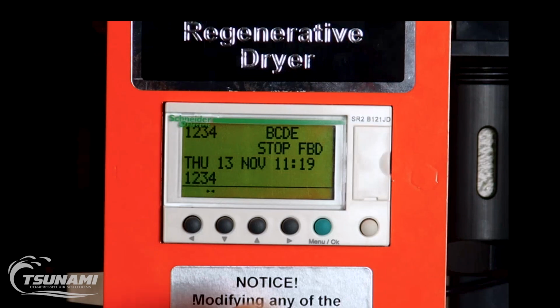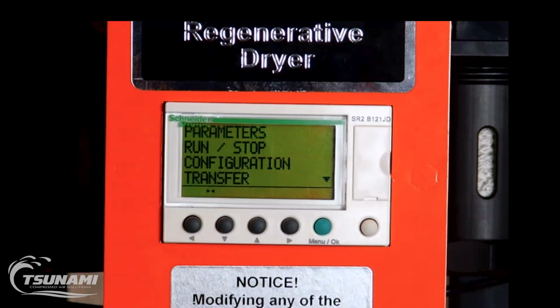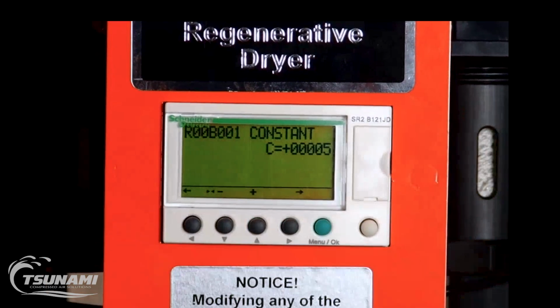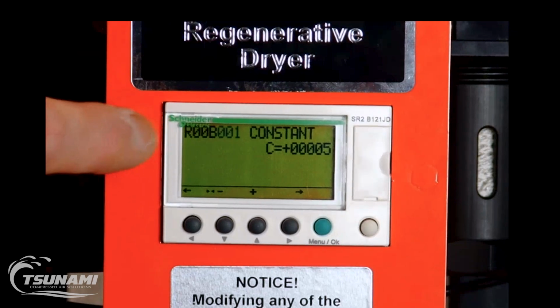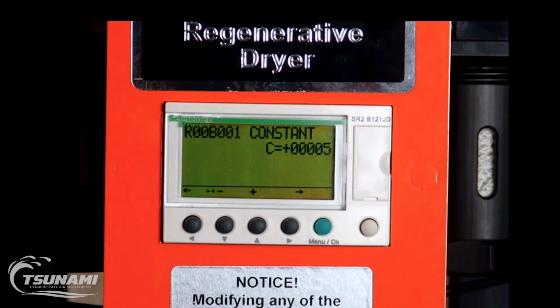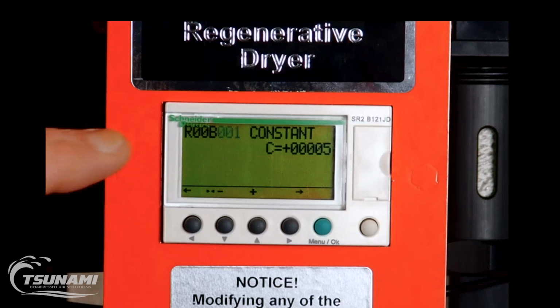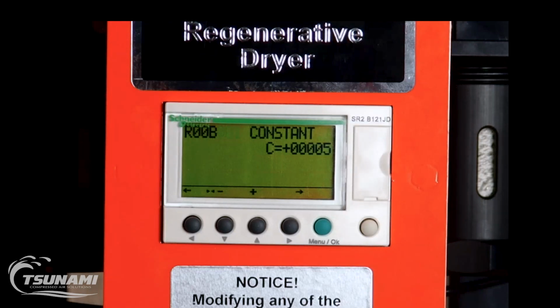Now that we're in the stop mode, we can access the parameters. Parameters is flashing. We hit the menu OK button again. To understand what the parameter screen looks like, it's R00B001. The important number is the flashing 001, that B standing for block. It basically is like the block. So block 1 has a value.